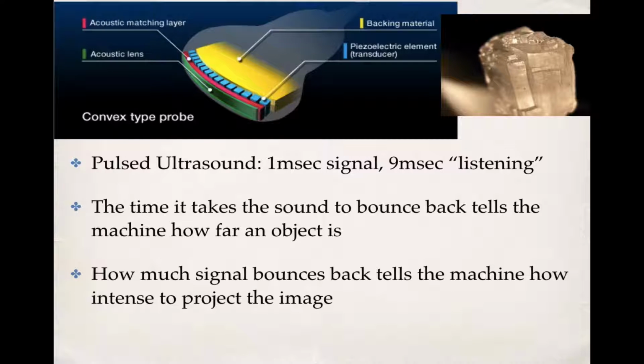And how it judges the distance of the tissue that you're trying to image, it's all based on the velocity, the speed at which the sound bounces off that tissue and then returns to the transducer. So it's recording those times, recording how long it takes for the sound waves to bounce back, and that's how you get tissues at distinct depths within your image. And then in addition to the time it takes for the sound waves to come back, how intense or how high the amplitude is of those waves returning to the transducer gives the machine additional information about what kind of signal it's getting back. So the more it gets back, the brighter basically the image will be. And then you can interpret that as understanding how dense the tissue is and what kind of tissue you're looking at.